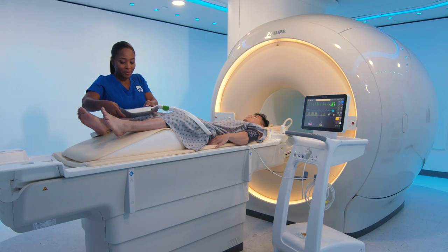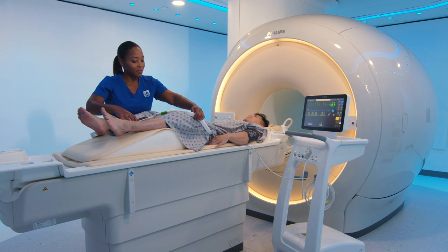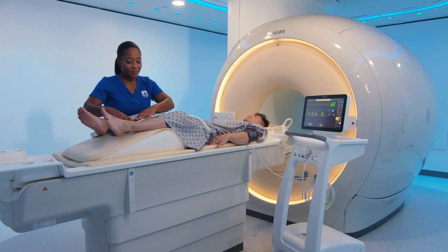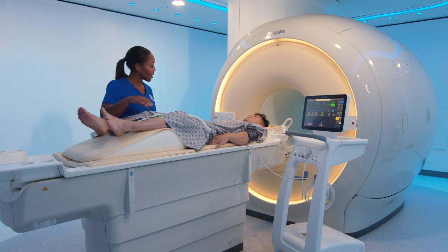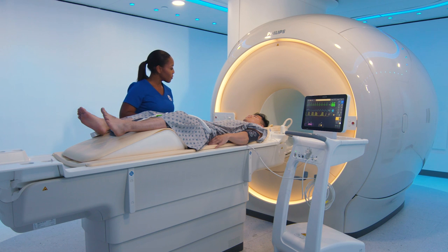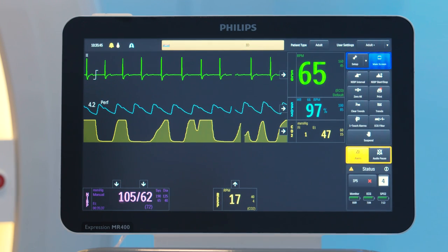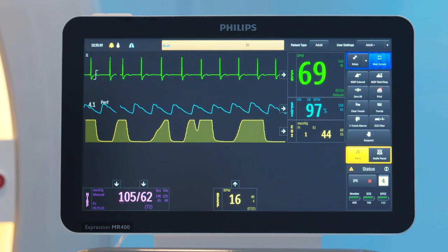Reducing the number of wires and electrodes connected to the patient may reduce the patient's risk for burns in the MRI and may be more convenient for workflow. The gating feature allows for MRI triggering and synchronization based on the measured ECG or SpO2 signal.